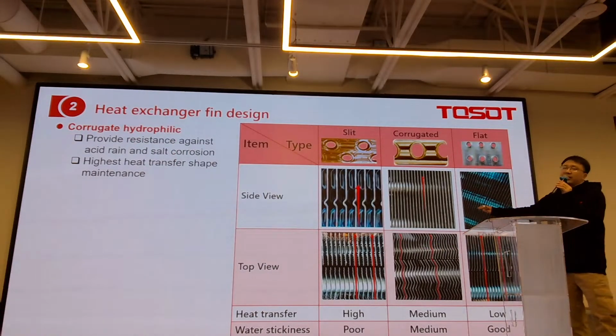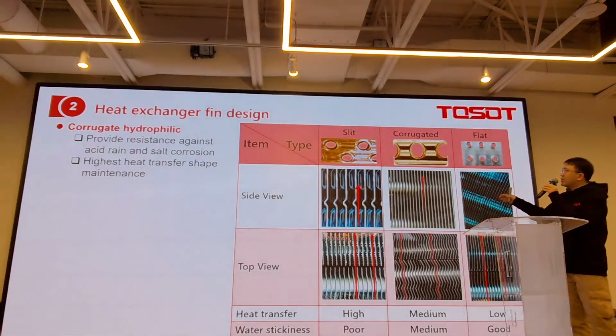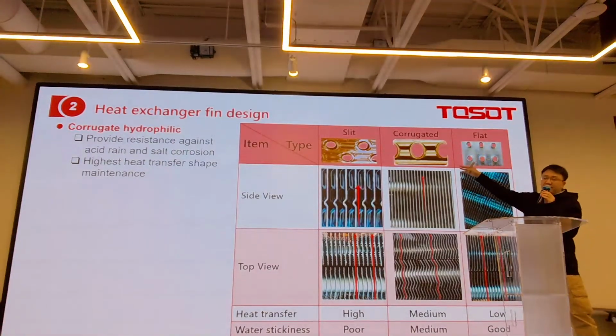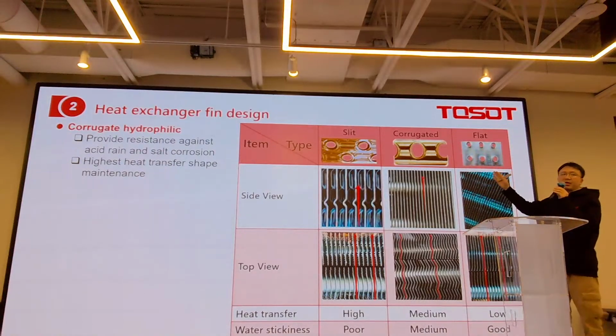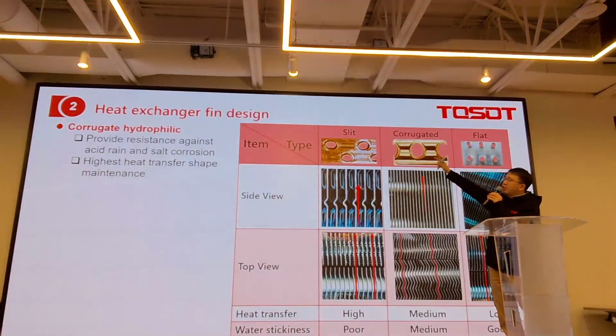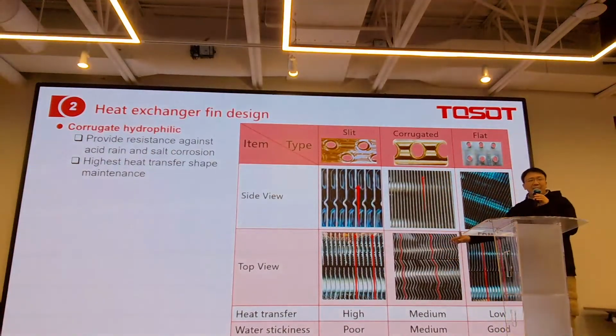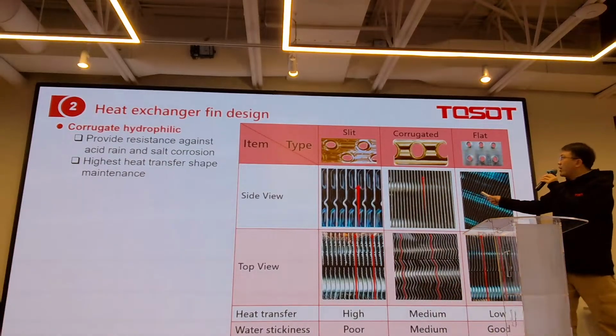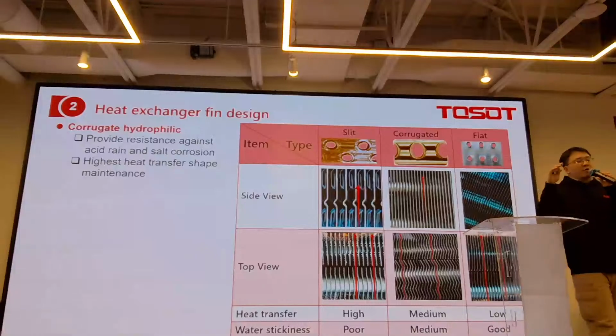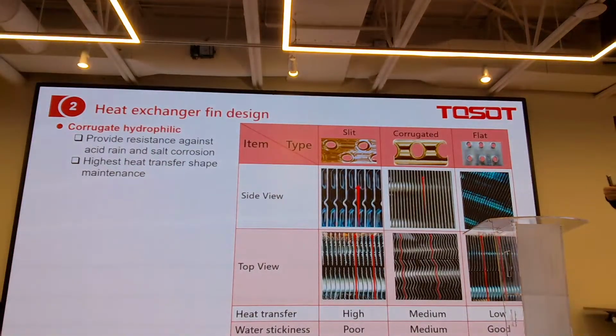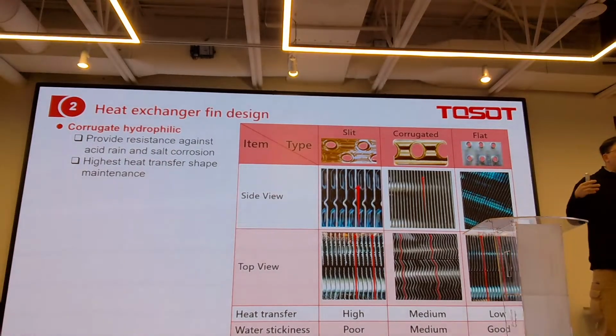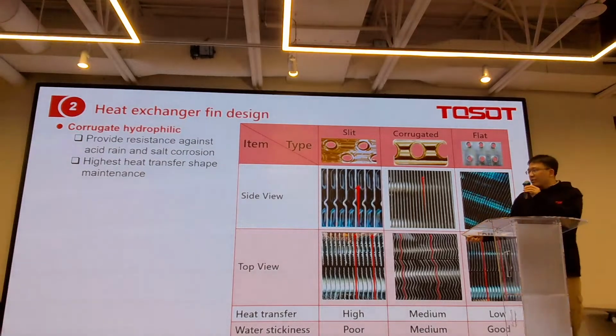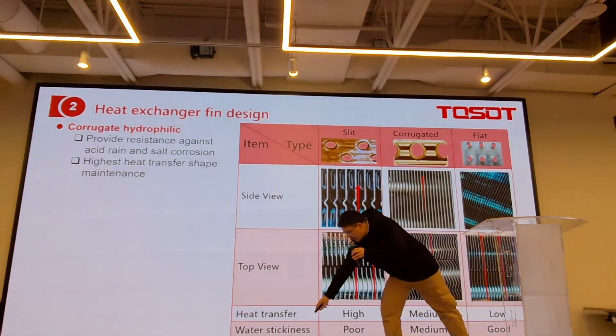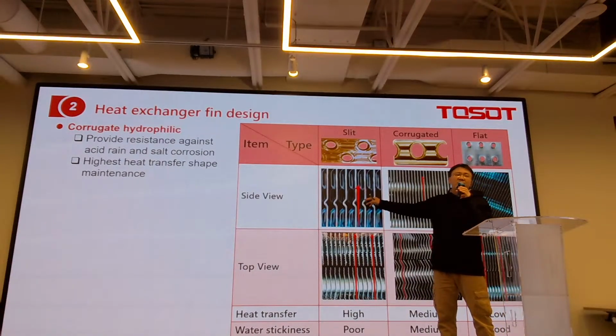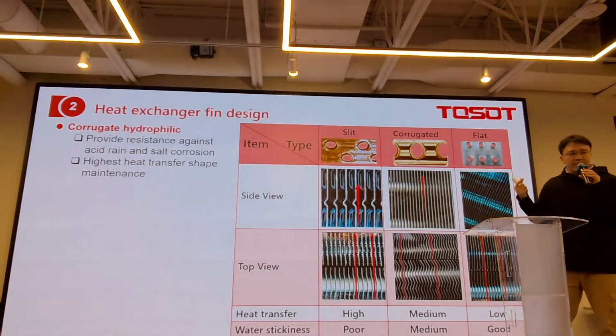And then we will go to the heat exchanger fin design. Actually, in the factory design system, you can find that we have these three structures. One is the flat, that means the surface is completely flat. The other is the corrugated, that means the surface goes up and down like this. And next is the surface where we cut many slits on it. The purpose of these two is just to increase the airflow. We need to make it more turbulent, and the benefit is for the heat transfer. As you know, if we make it more turbulent, the heat transfer efficiency will be higher. So from this comparison, for heat transfer, this one is definitely higher, right? Because we can make the airflow more turbulent.